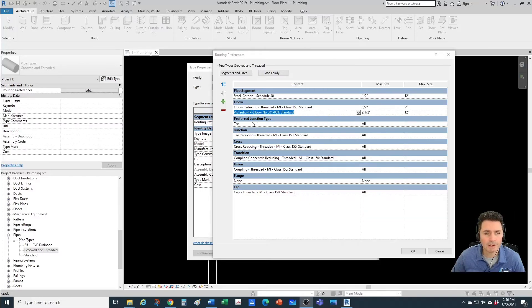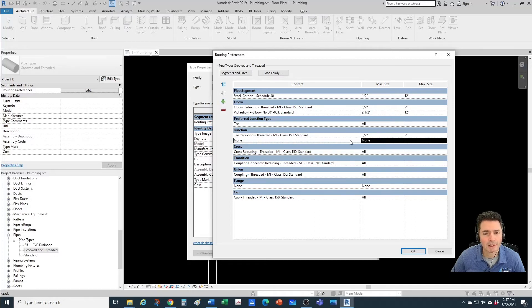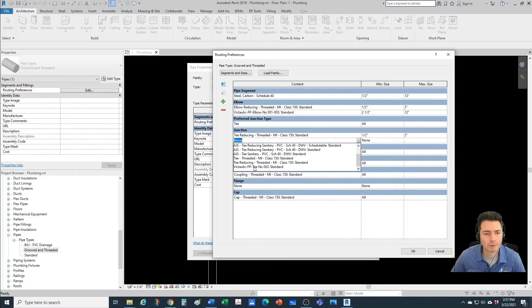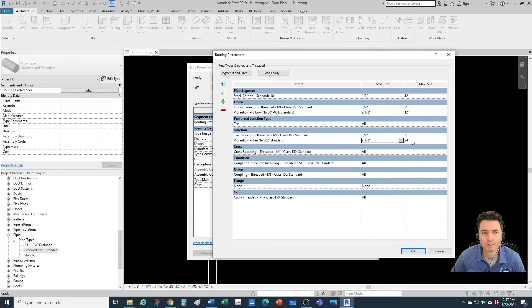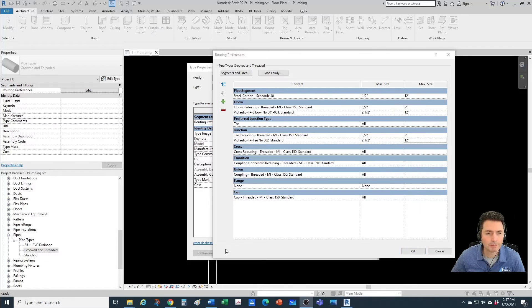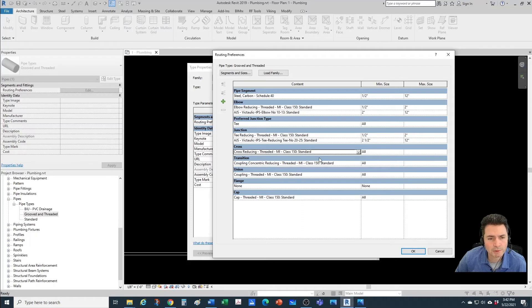For our T, we keep the preferred junction method as T. Similarly, from half inch to two inches we have the threaded type, then we add another category for the grooved Victaulic T from two-and-a-half inches to 12 inches. For the cross we do something very similar: half inch to two inches gets the threaded reducing cross, then we add the grooved one.